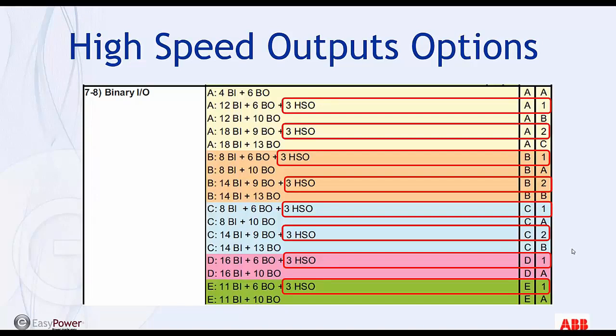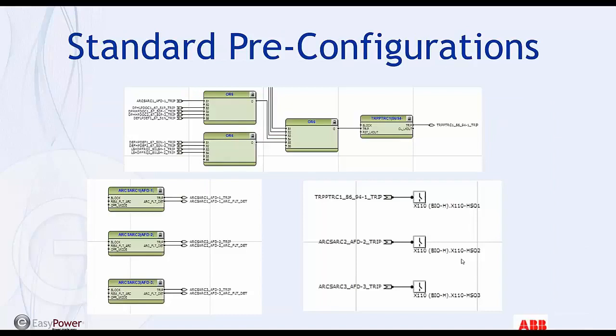Because even an additional 10 milliseconds can make quite a difference. So that's definitely worth it for a small additional price. If you're going to use arc flash, then you need to use high-speed outputs, and all of our default logic is set up such that you are using the high-speed outputs, and you have the pre-configured logic for your arc flash detection system, as you can see here, arc flash detection. So you don't have to configure any of the logic. Everything is already programmed for you, as long as you select the right relay.